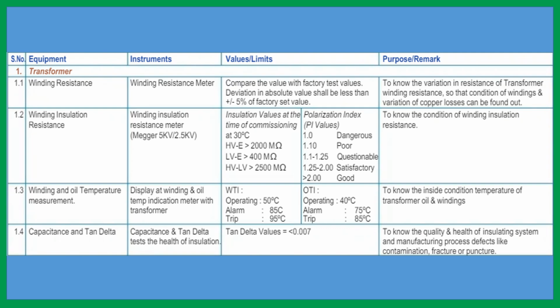Winding and temperature measurement. The alarm must be at 85 degrees centigrade for windings. The winding temperature indicator at 85 degrees should give the alarm, and trip at 95 degrees centigrade. The circuit breaker will trip at 95 degrees centigrade. Okay, both the transformer HVCB and LVCB will trip. And for oil, 10 degrees less. That means alarm at 75 degrees centigrade and trip at 85 degrees centigrade.